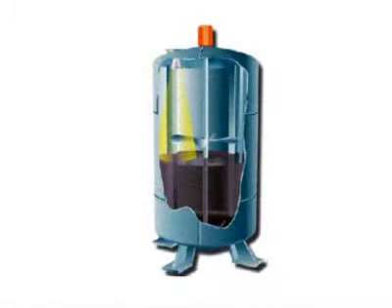A process engineer in a chemical or pharmaceutical plant looks at the reaction happening inside a reactor vessel and not the fact that because the reactor is sparged or agitated, it's exceedingly difficult to measure the level in the reactor. In fact, in the case of an agitated reactor, there is no level when the agitator is running. There's a vortex.